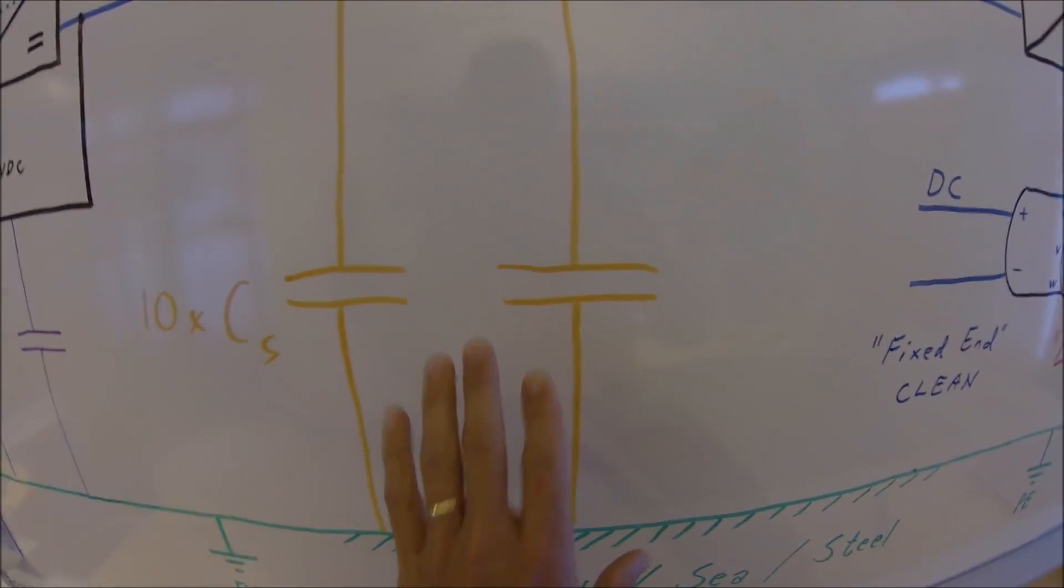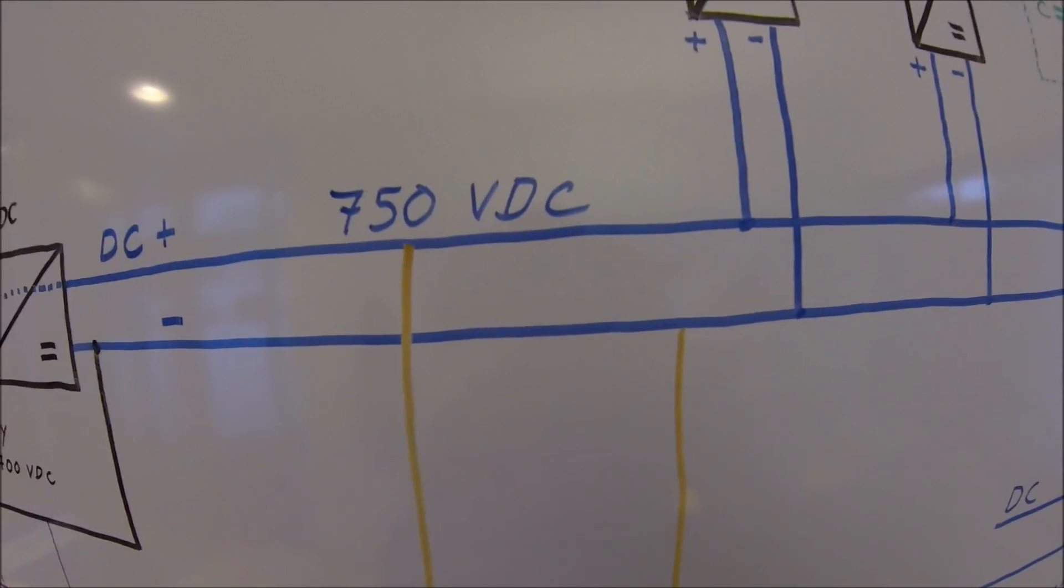The total stray capacitance in all these cables and transformers should be one tenth of the capacitors that we install on the DC bus.